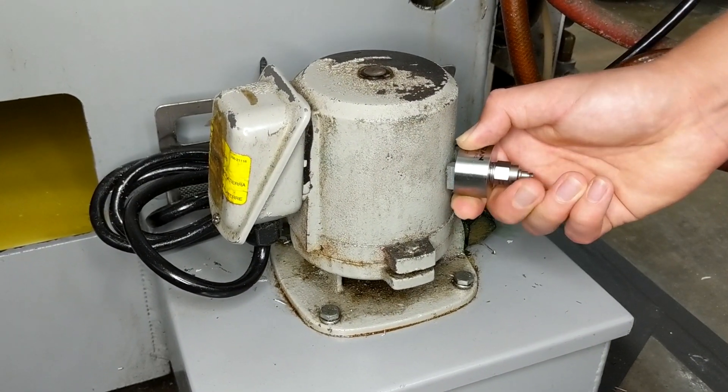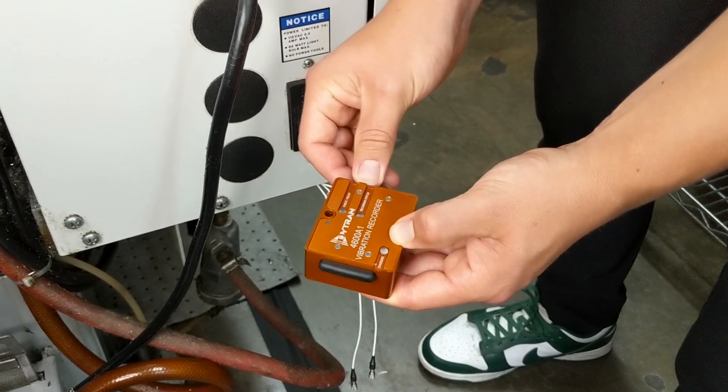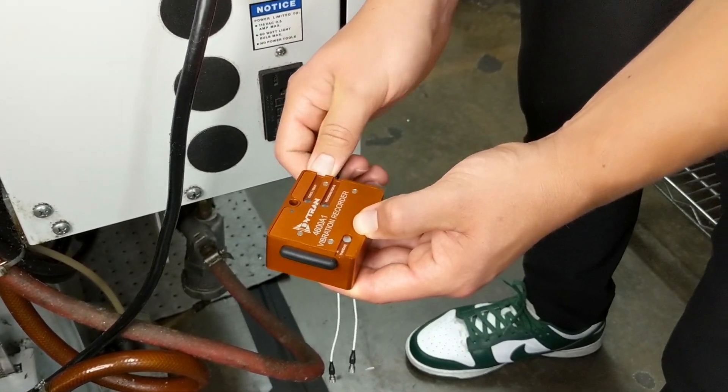To measure this vibration, we mounted general-purpose Dytran accelerometers to each coolant pump. These accelerometers are connected to the input channels of the Dytran 4600A1 vibration recorder to sample the recorded vibration data for each CNC machine continuously for the duration of one week.